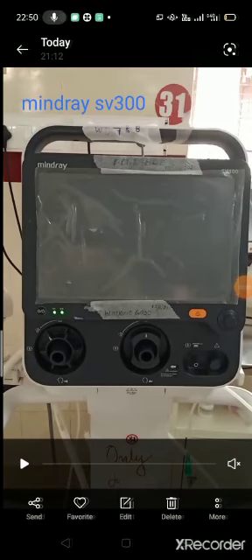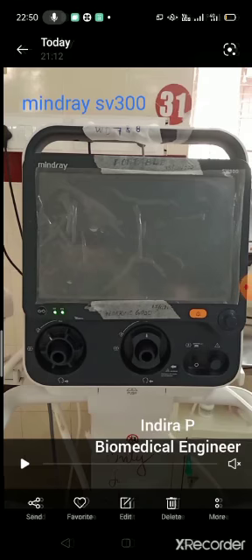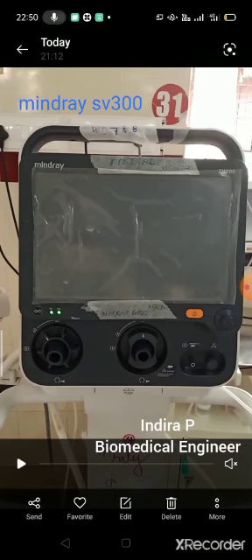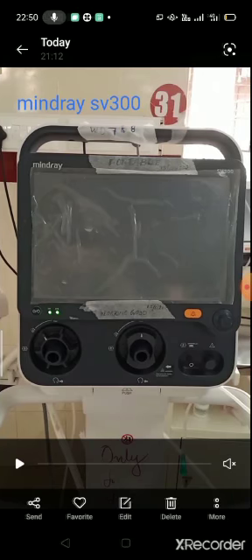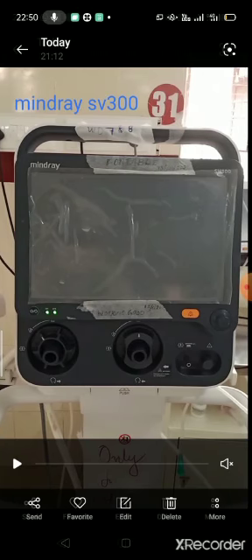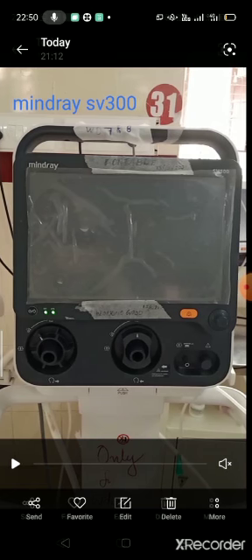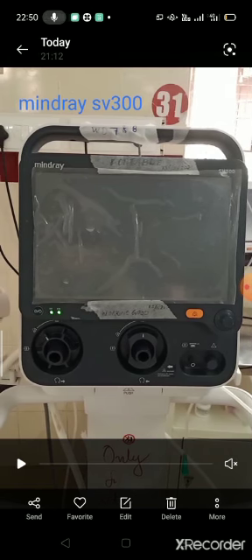Okay, this is a SV300 ventilator. This ventilator can be used as both a portable and a standalone ventilator. You have one port at the center, which is an inspiratory port, and you will connect the inspiratory limb of the tubings to this port. You have another connection at the left side, where you will connect the expiratory end. Both the valves, these are the exhalation valves, need to be in locked position when you connect the patient circuit.